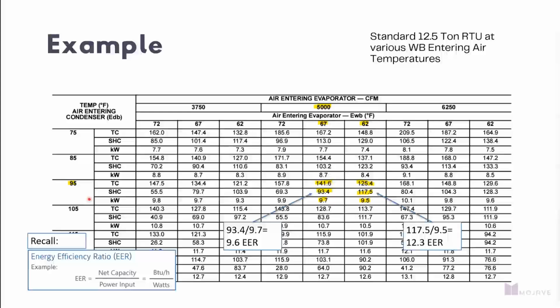At 95, 80, 67, 5,000 CFM, you could calculate your sensible efficiency at 9.6 EER. If we take that same condition air, 95, 67, but provide a drier version of that air, so at 62 wet bulb instead of 67 wet bulb, you actually get a higher sensible efficiency at 12.3, so that unit's going to run more efficiently because you're not trying to condense moisture on a coil.